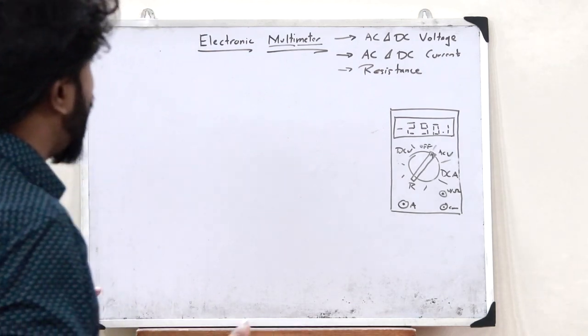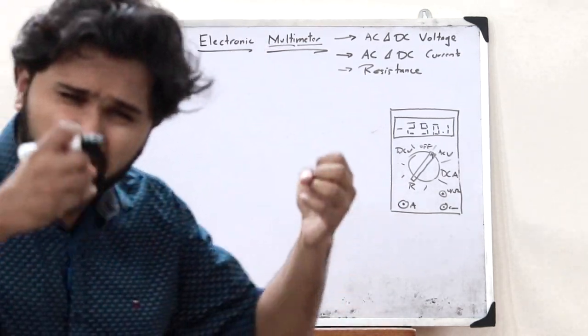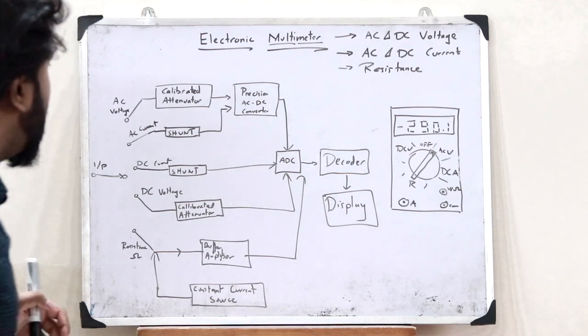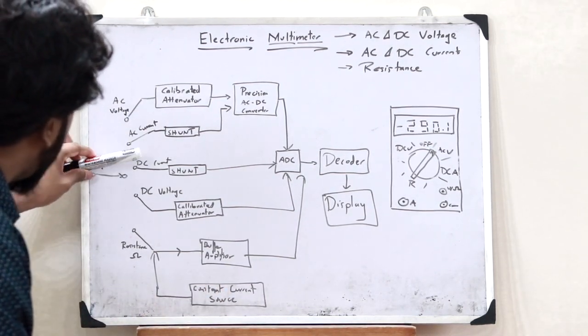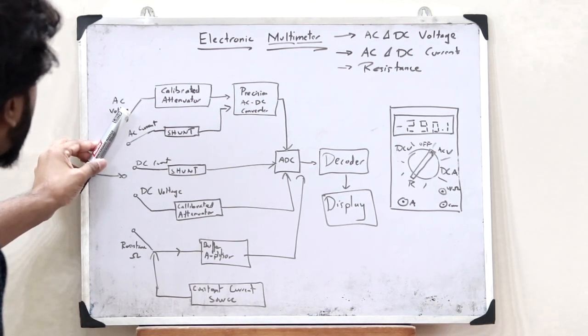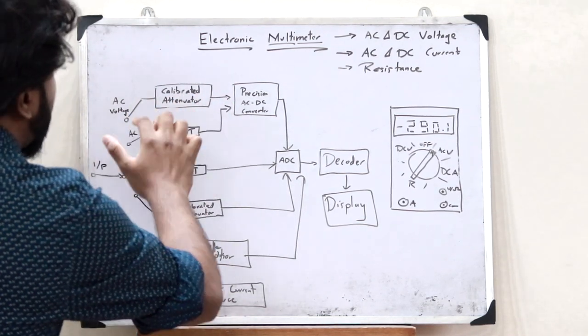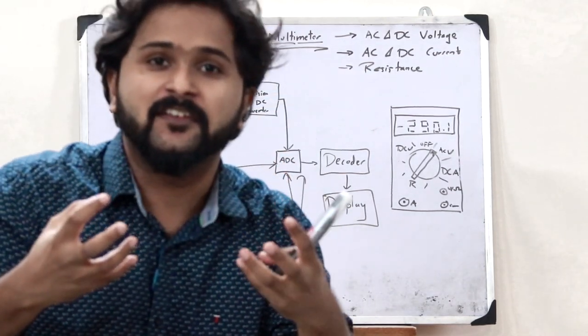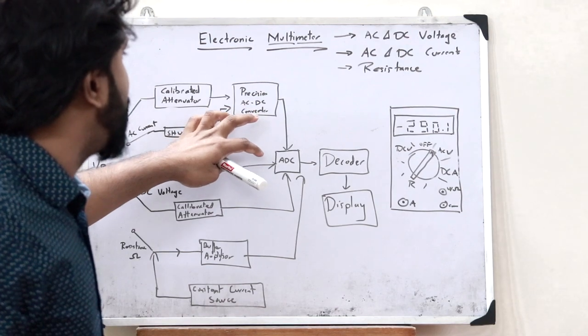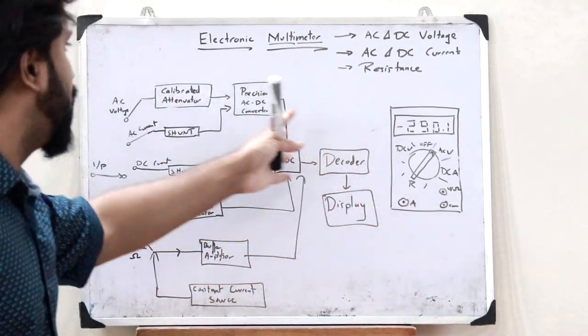Now we need to know the inside block diagram of this multimeter — what components are present inside. This is the basic block diagram of the digital multimeter. The rotating knob is shown here. When rotated to AC voltage, the AC voltage is passed to an attenuator, which is a device that reduces the power without distorting the signal. It reduces this power and passes it through an AC to DC converter, which is then passed through an ADC and then to a digital display where we can obtain the digital reading.